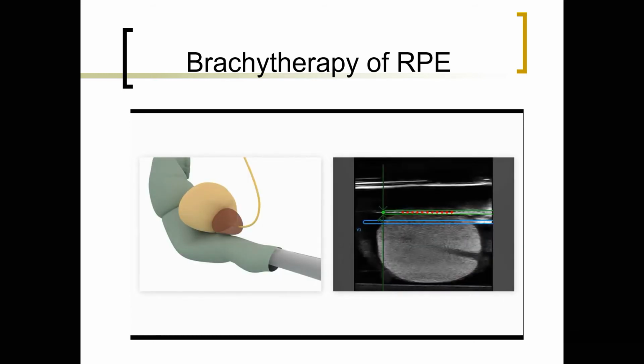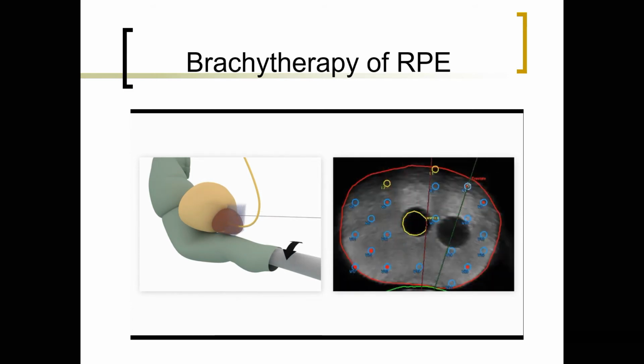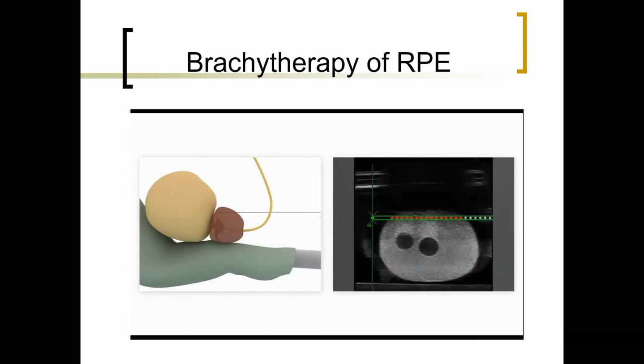The needle navigation technology helps you to insert the needle in the planned trajectory. Simply select the needle you want to insert, and the probe will automatically be rotated to the correct plane. As a result, you can follow and guide the needle insertion live on the ultrasound image. Once in place, simply reconstruct the exact needle position and update your plan.